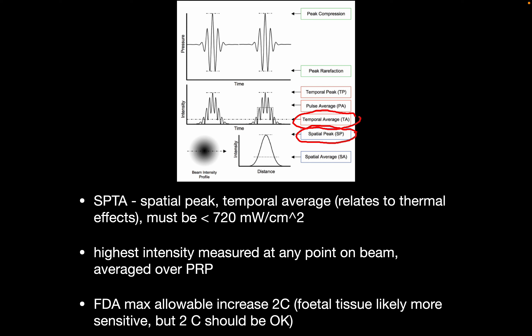Most likely the fetal tissue will be more sensitive to thermal effects. However, the maximum 2 degrees Celsius increase should be okay for fetal tissues as well. So for the moment, that applies to fetal tissues as well. Let's move on to the mechanical effects. Mechanical effects are the cavitation and microstreaming.